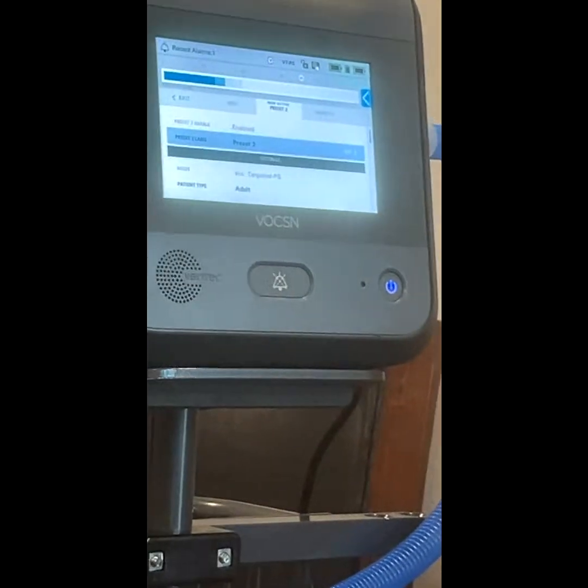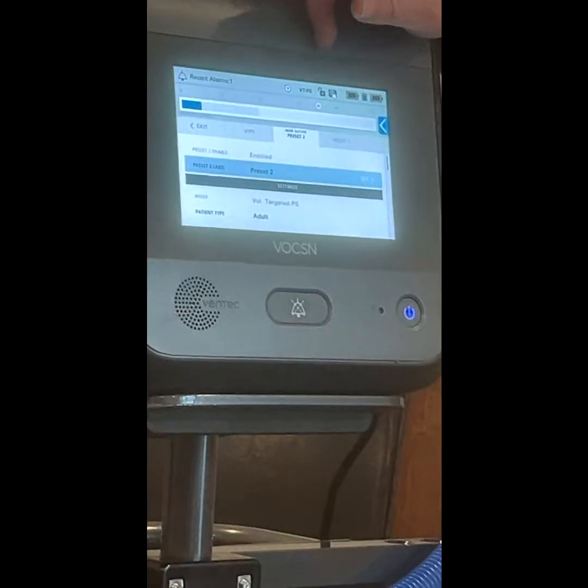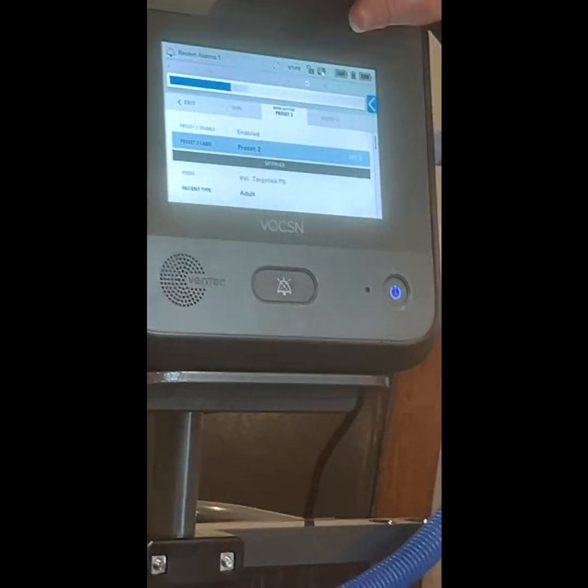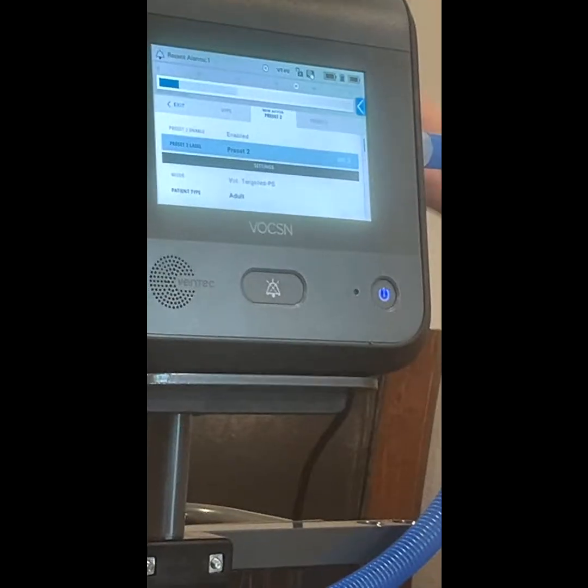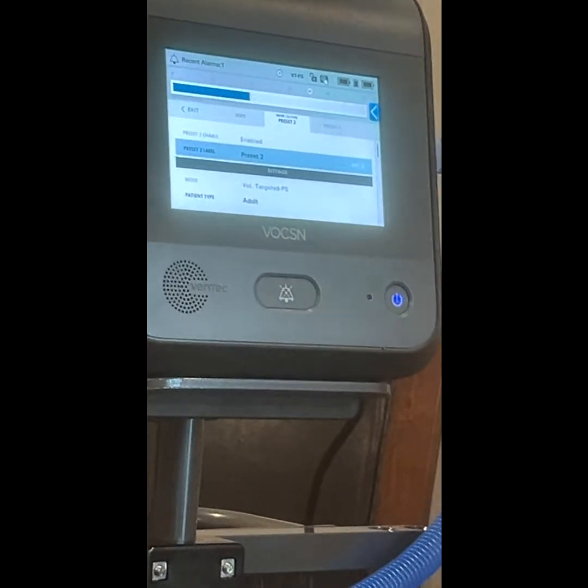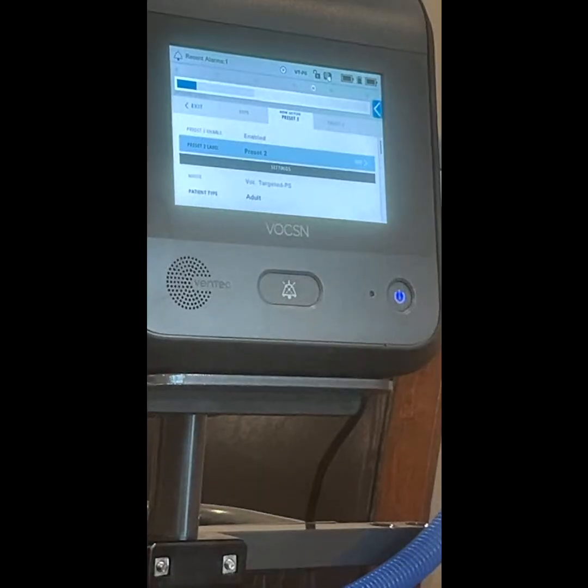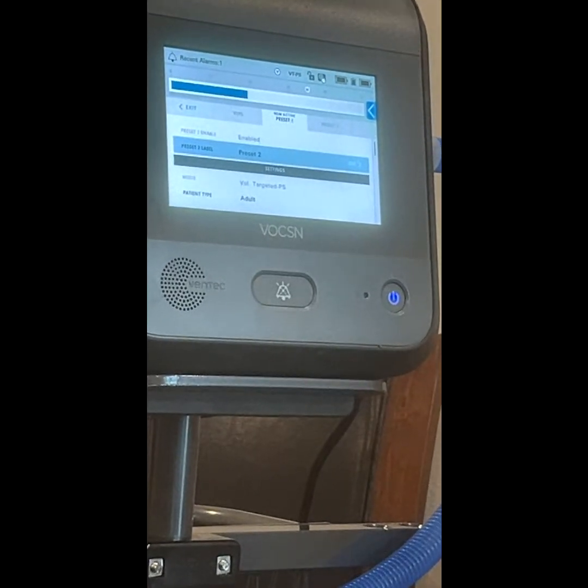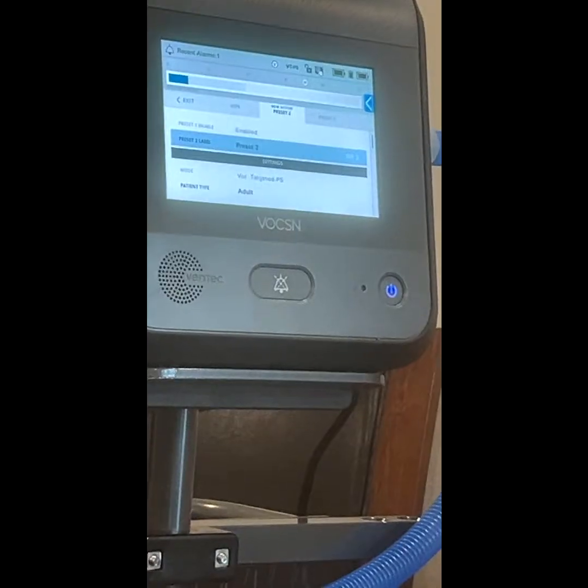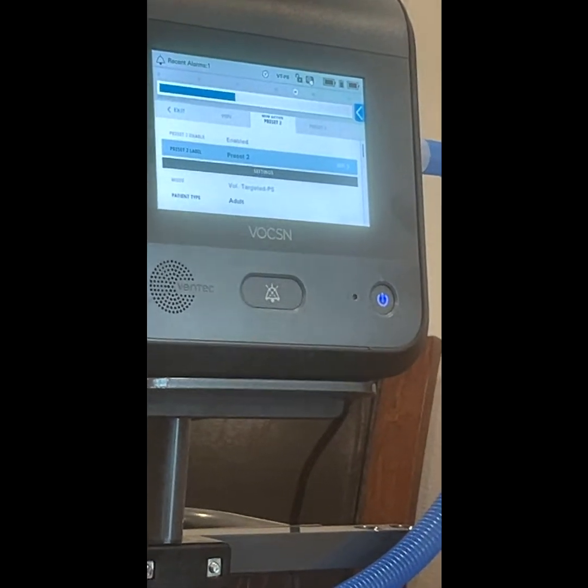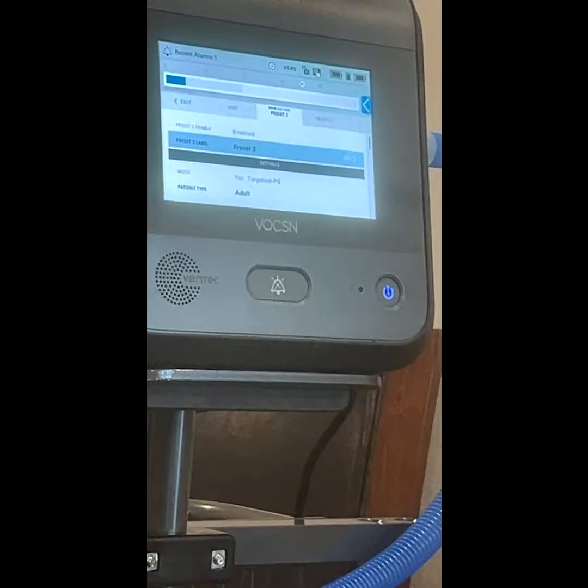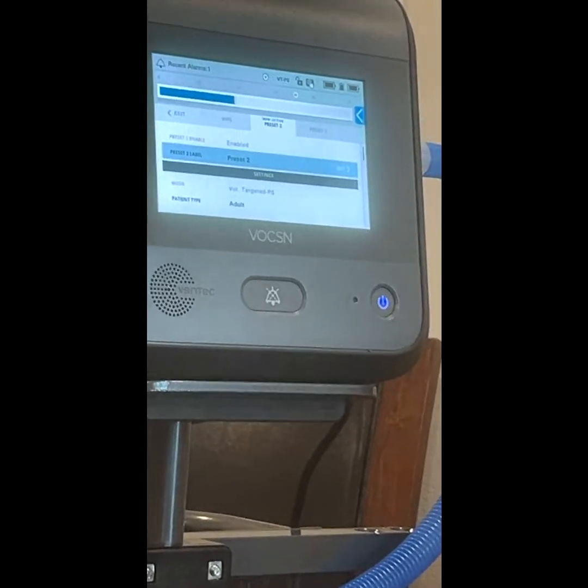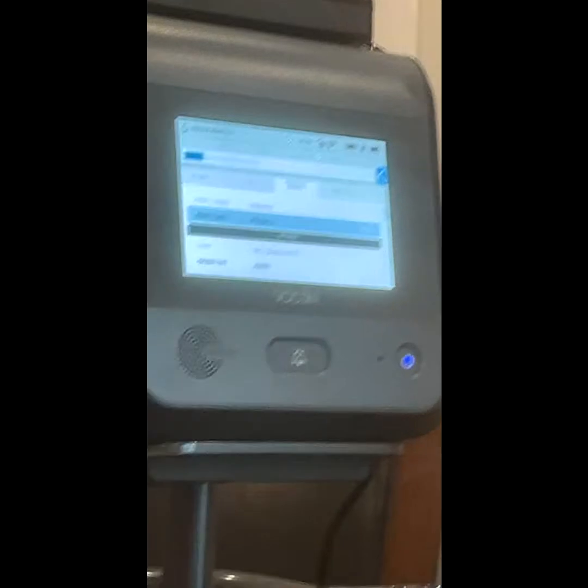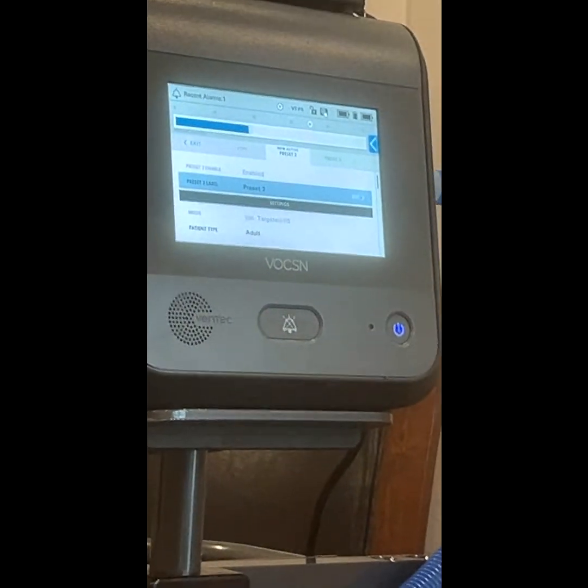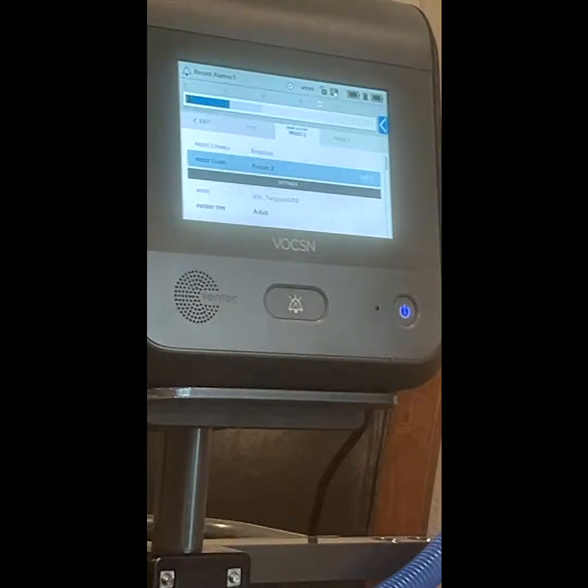If you go to your menu, you can go to your settings and alarms, and it'll tell you have 3 presets. You got 1, 2, and 3. That's if you have a different mode during day and a different mode at night and whatever. Now, the only one that has a massive amount of different modes is the Evo. It has at least 8. Yeah. Trilogy only has 2, primary and secondary. This has 3. LTV doesn't have it. You have to eliminate something. Okay.